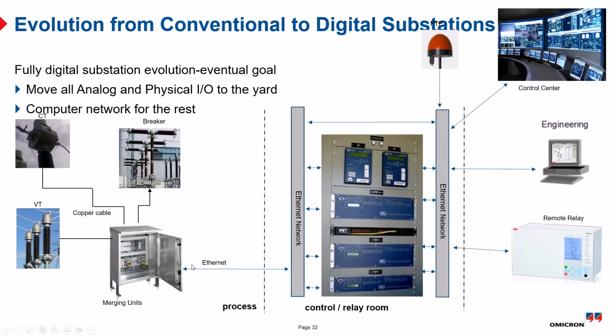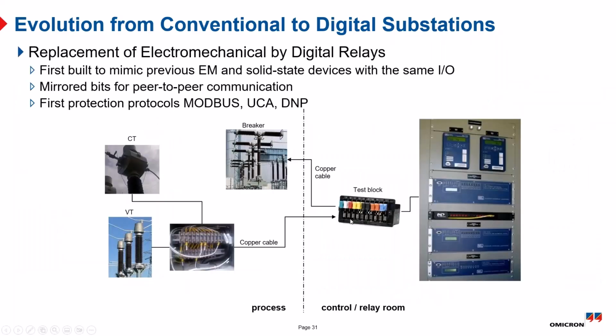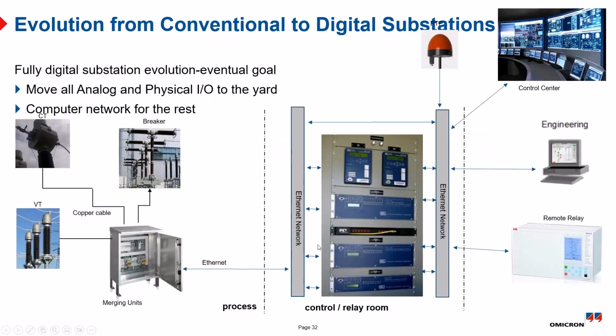And then going back in the substation, instead of all this copper, we're going to have one Ethernet cable. It's going to plug into a network. In this case, this is the process bus, and all the values are going to be read by any protective device that's programmed to listen to them. So you are not going to have all those miles of copper, CT and PT and input and output wires anymore. You're just going to have Ethernet going to a switch, and then each protective device plugged into a switch. On the other side, there's another Ethernet network where all the binary IOs go out.